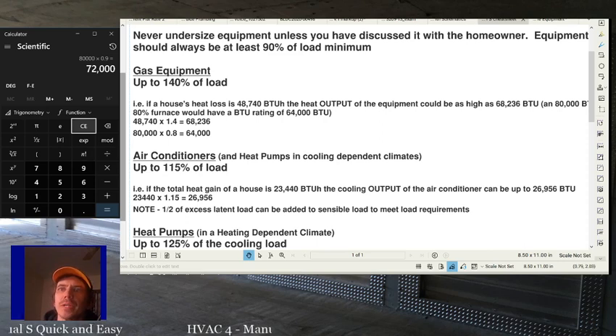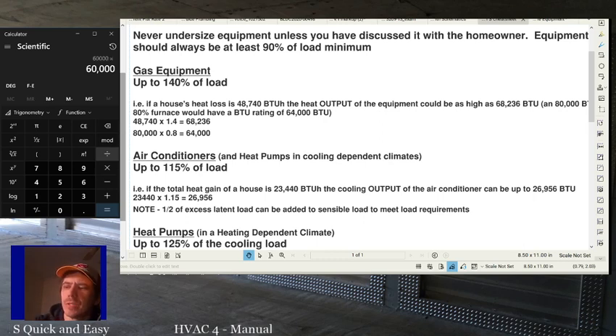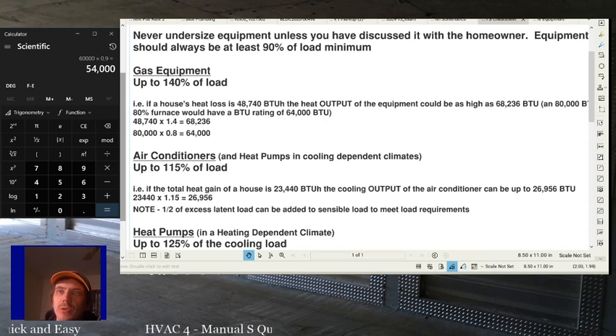So if we were moving to a 90% furnace, we would actually want to go to, I think, say it came in 60,000 BTUs. Some of them come in 60, some of them come in 70, but 60,000 times 0.9 would actually be 54,000 BTUs. So if you were going 80%, you would want an 80,000 BTU furnace, but if you were going 90%, you would want to go down to a 60,000 BTU furnace. And that's not actually that uncommon for the efficiency to change the size of the equipment you're going to want to install. So that's something to keep in mind.